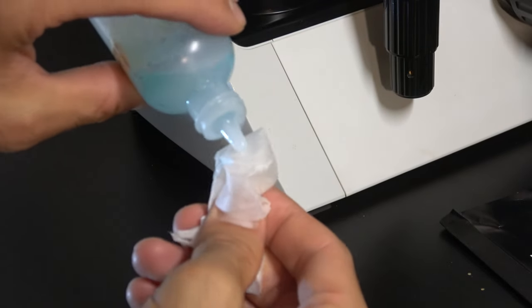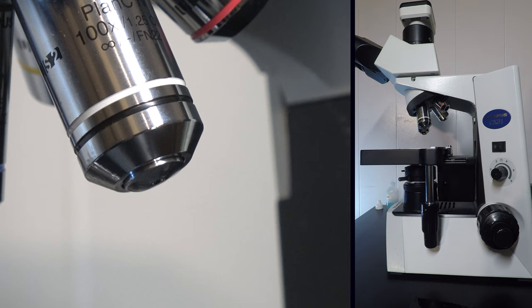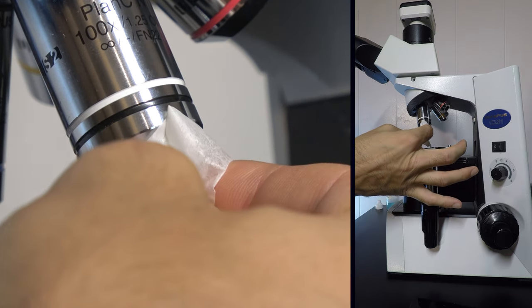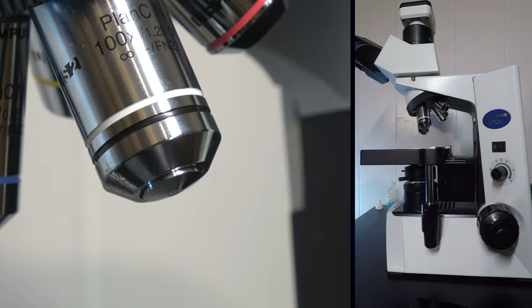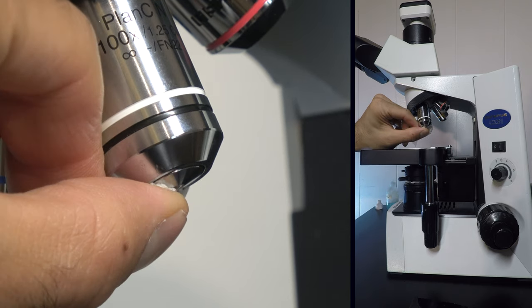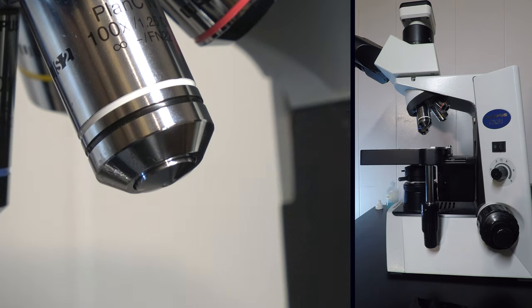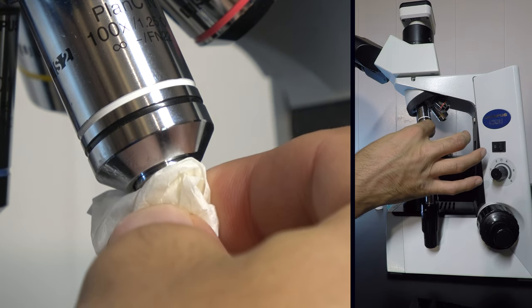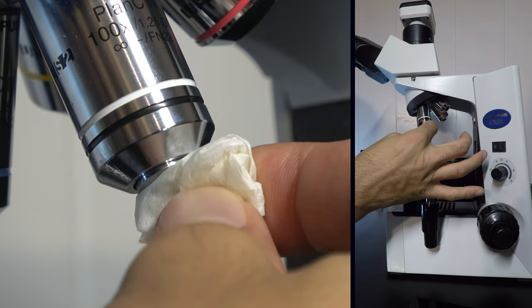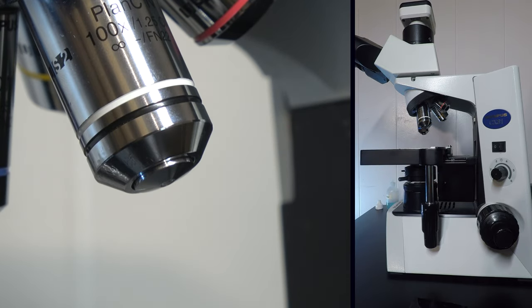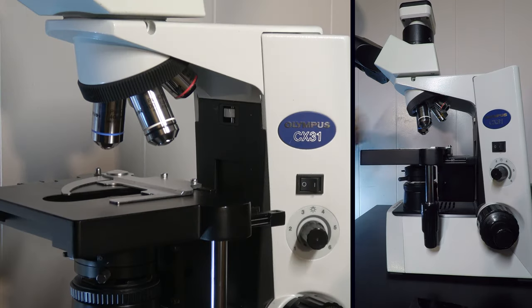Add a few drops of lens cleaner and proceed to gently wipe the lens. Try not to run the same area of paper over the lens twice. Also notice that the objectives have a spring loaded retractable nose cone to protect the lens from damage. Make a pass with a dry piece of lens paper and that will take care of the lens itself. Proceed to remove oil from the objective body as well before moving on.